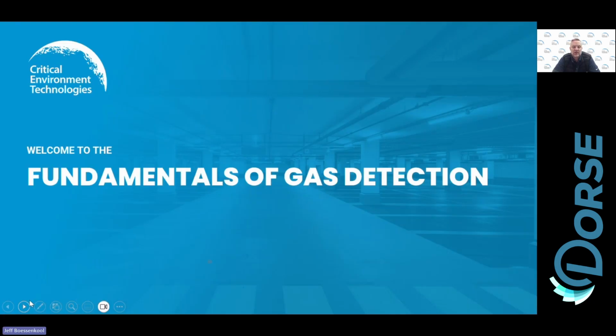Asphyxiants, what we're talking about here is percentage volume of oxygen in the air, right? So what's the typical percentage of oxygen in the air in your building or outside? It's about 21%, right? 20.8, I think. And we can measure both a high level of oxygen, which could lead to combustibility, as well as a low level of oxygen, which could lead to asphyxiation. And one of the applications here that I find quite interesting, you'll see this a lot of times in laboratories, where an early warning sign of a gas leak would be the depletion of oxygen.